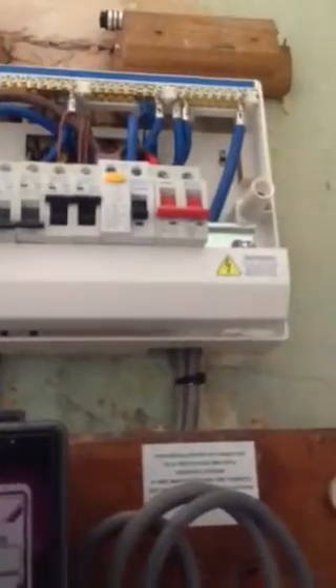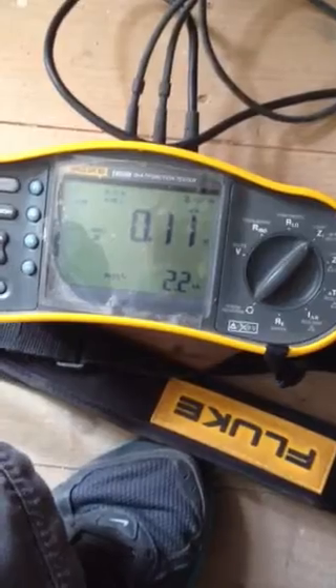With it being a TN-C-S system, we expect to achieve a value of less than 0.35 of an ohm, and I'm going to just repeat the test. It's always good to repeat it, and we'll take the higher of the two readings. And we've got 0.11 of an ohm. So that's an earth fault loop impedance test. We're going to replace the earthing conductor.